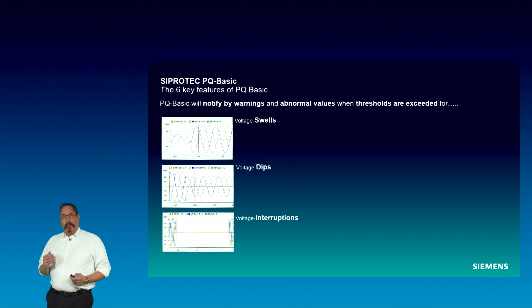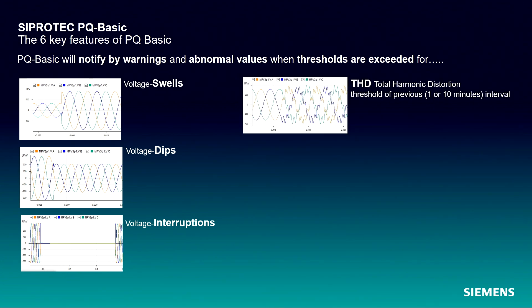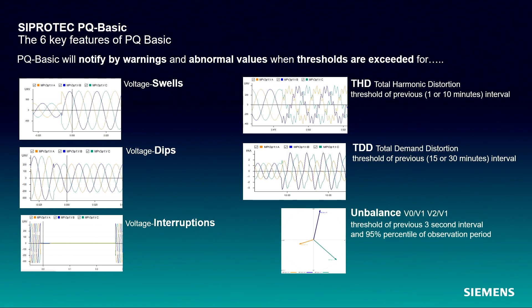Furthermore, observation intervals are provided for the total harmonic distortion (THD), the total demand distortion (TDD) — the ratio of the harmonic content expressed as a percent of the maximum demand current — and last but not least, the voltage unbalance.